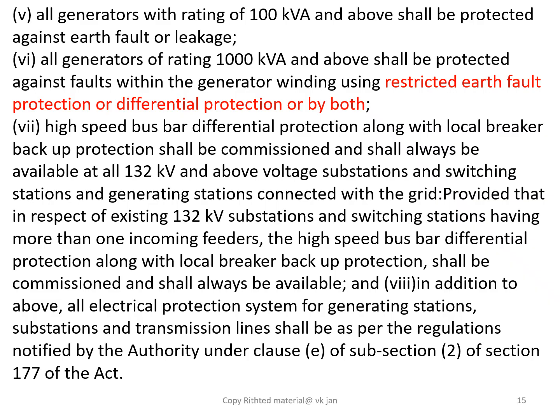Friends, all generators with rating 100 kVA and above shall be protected against earth fault or leakage current. Next, all generators of rating 1000 kVA and above shall be protected against fault within generator winding using restricted earth fault protection or differential protection or both.